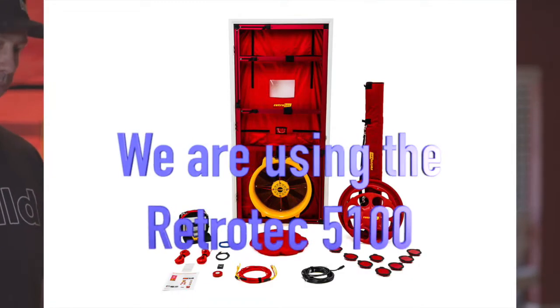So what are we doing today, Ken? Today we are first going to get the blower door running. We're going to run a quick test to check the house. I heard this thing has a lot of leakage — we actually ran another blower door test before and I know the number, but I'm withholding so you can see what it comes in at. Then we're going to slow the blower door way down and try to draw in all that Texas heat across the building materials to look for where the air leaks are actually coming in, using an infrared camera. We do have a bit of an issue though — two AC units, one working, so we don't have a lot of temperature difference to work with, but we have some.